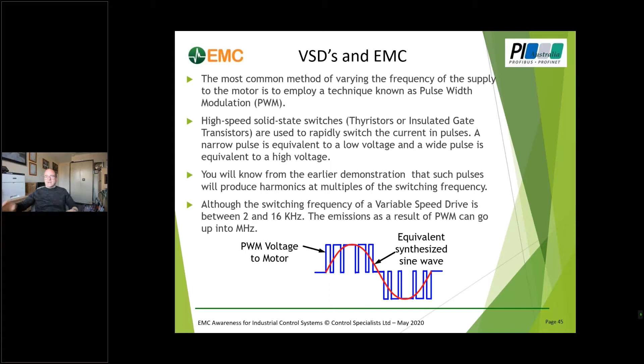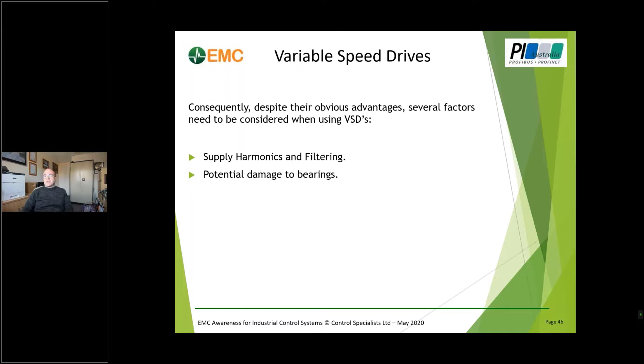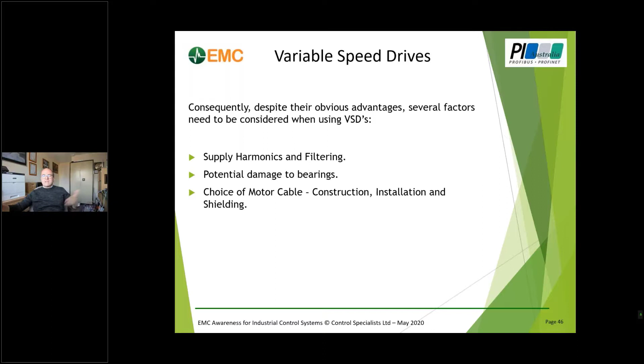Despite their obvious advantages, there are a number of disadvantages we can cater for as long as we're aware of them and follow the guidelines. We have supply harmonics and filtering — most people are aware of that. There's potential damage to bearings, which some people aren't aware of. And then there's the issue on the motor side: choice of cable, general construction, bonding, shielding, etc. We see all sorts of things here.